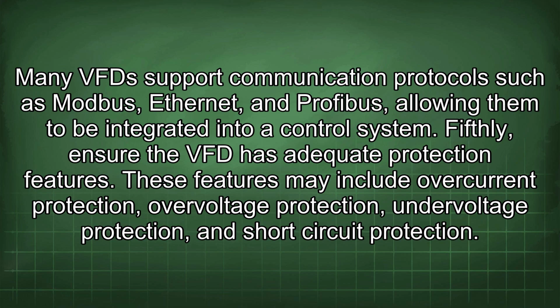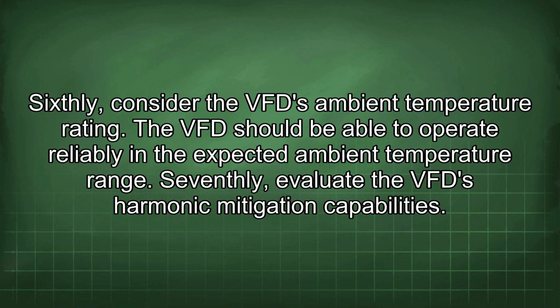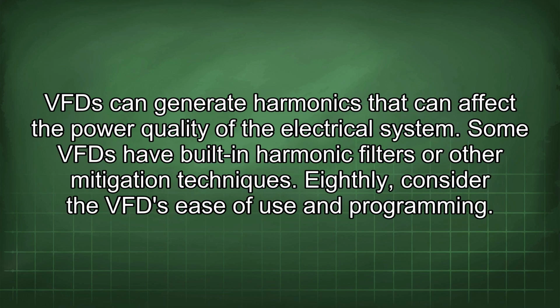Fifthly, ensure the VFD has adequate protection features. These features may include overcurrent protection, overvoltage protection, undervoltage protection, and short-circuit protection. Sixthly, consider the VFD ambient temperature rating. The VFD should be able to operate reliably in the expected ambient temperature range. Seventhly, evaluate the VFD harmonic mitigation capabilities. VFDs can generate harmonics that can affect the power quality of the electrical system. Some VFDs have built-in harmonic filters or other mitigation techniques.